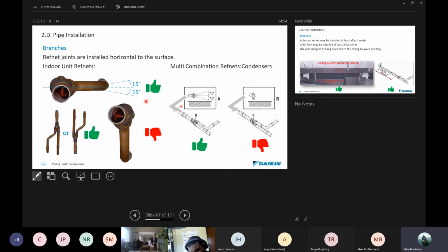As we said earlier on, RefNet joints can only be installed horizontal. If they're in the horizontal plane, both pipes must be level. You can install RefNets for indoor units in the vertical plane, but here you see both of them must be in the same plane. You cannot do this. So just keep that in mind. Here again, the RefNet is horizontal. It may not be like that, where the pipe is one above the other on the branch. Guys, you get this right, because as much as we talk about this, we still come across sites where this has happened.